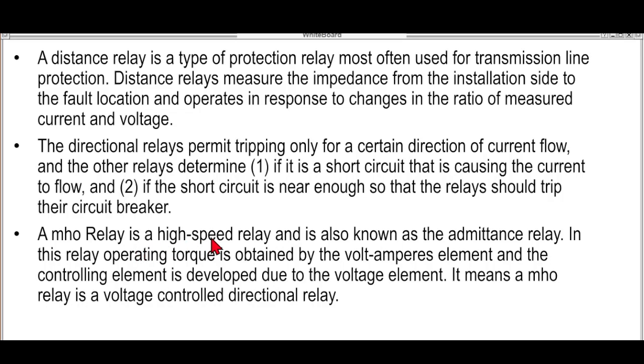Meanwhile, the mho relay is a high speed relay and is also known as an admittance relay. In this relay, operating torque is obtained by volt-ampere. So it means a mho relay is a voltage controlled directional relay. If the fault is nearer and very large, it will trip faster compared to the directional relay.